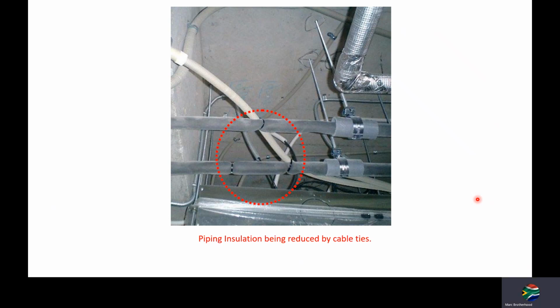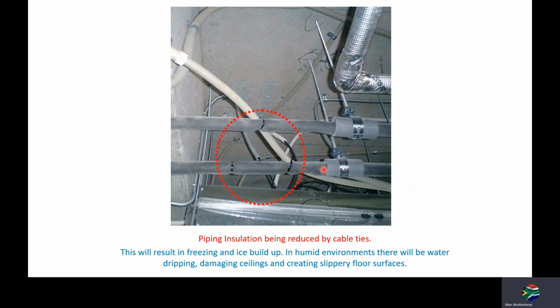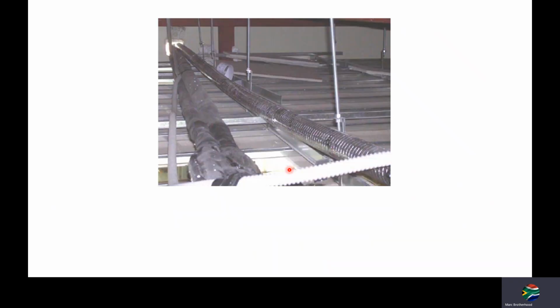Piping insulation being reduced here with cable ties or tie straps, and that's ultimately going to result in freezing and ice buildup. Because you've reduced the cross-sectional area of the insulation material, these tie straps and cable ties are ultimately going to act as mini evaporators. So in humid environments, there will be water dripping. It's going to damage ceilings, and if it's in an open environment, let's say in a car park, all the humidity in the car park is going to create evaporation, and these are going to drip and they're going to wet the floors and create slippery floors in undercover car parks.